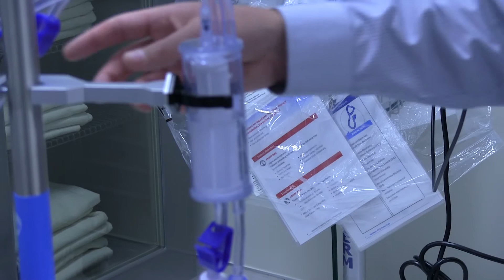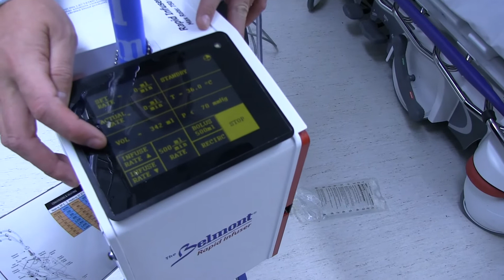So it's easy enough. You say, okay, we ran dry, open back up your saline, press reprime, and then it does a 100 mL countdown from the beginning, and all that air that was introduced gets forced back up and out the vent. So in 12 seconds, you're cleared back out without having to disconnect from the patient. Right back to your operating screen. So we know we've got 342 cc's to the patient so far.